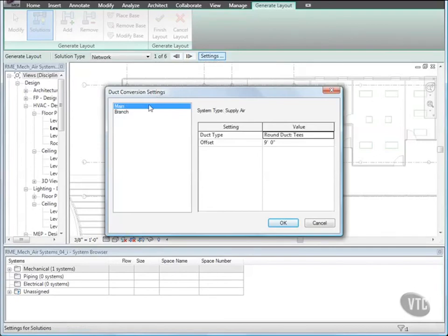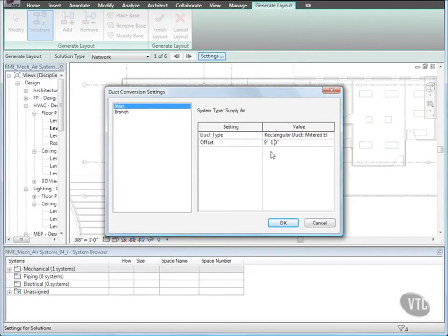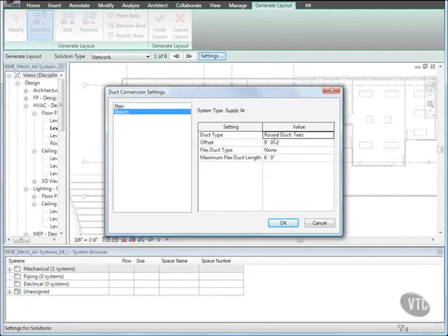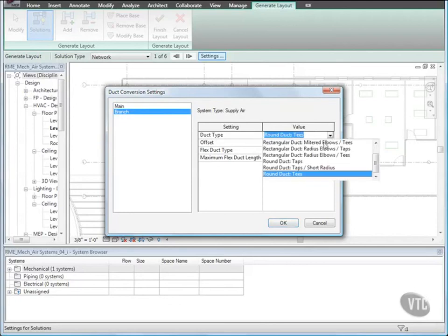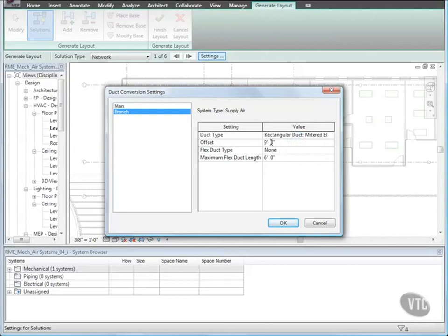Display Solution 1 and click Settings in the Duct Conversion Settings dialog. For Main, for Duct Type, select Rectangular Duct, Mitered Elbows and Tees. For Offset, type 9 feet 10 and a half inches. Then select Branch, and for Duct Type, select Rectangular Duct, Mitered Elbows and Tees. For Offset, type 9 feet 10 and a half inches. For Flex Duct Type, select Flex Duct Round. And for Maximum Flex Duct Length, enter 3 feet and click OK.